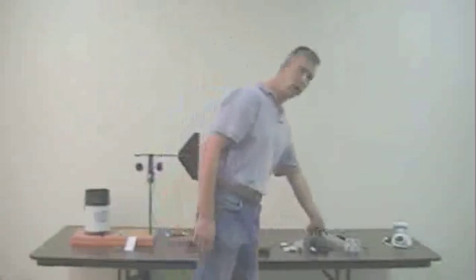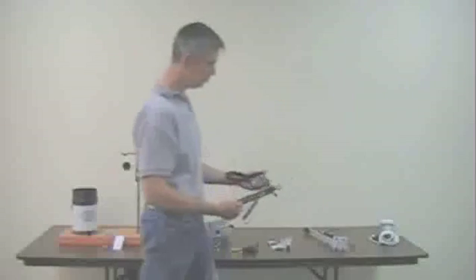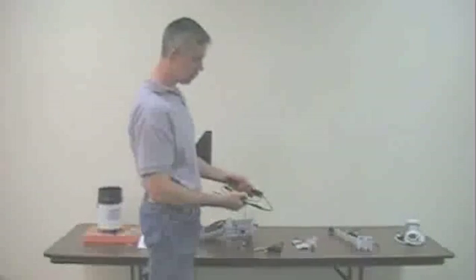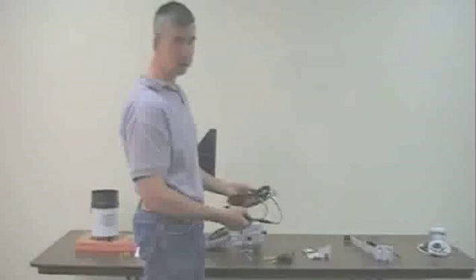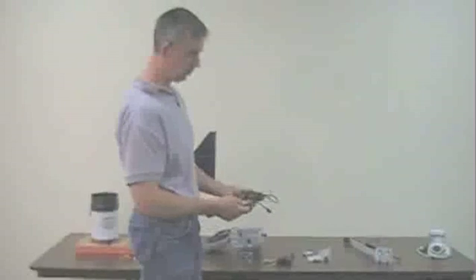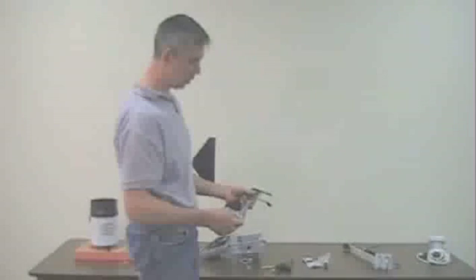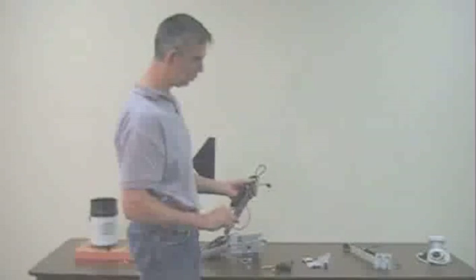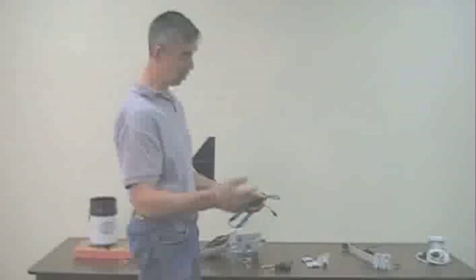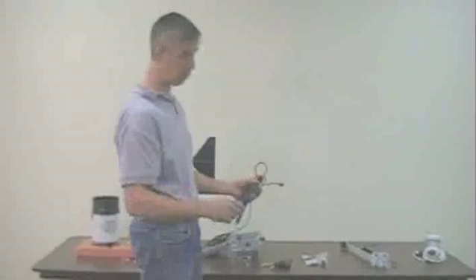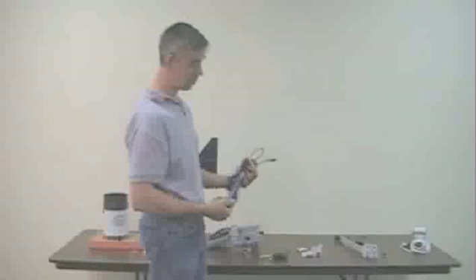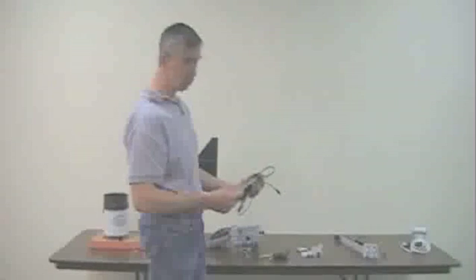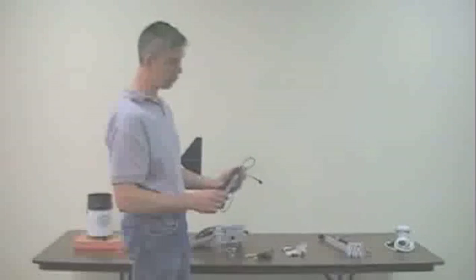Here we have our soil moisture probe. And once again, you want to plug it in and see that you get a reading on the computer. If you really wanted to ensure that it was working correctly, you could have a little pot filled with some potting soil or whatnot. You know, maybe grab a plant from the receptionist's area. Stick it in there and then water the thing and see if the reading actually changes.